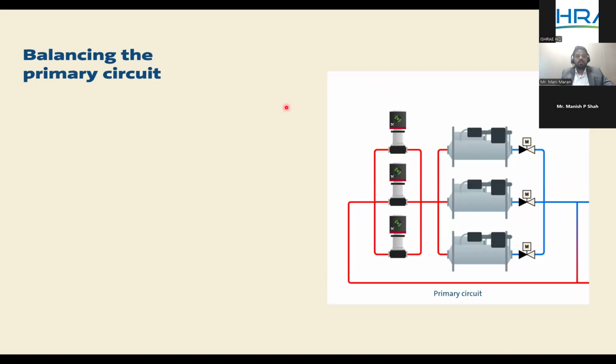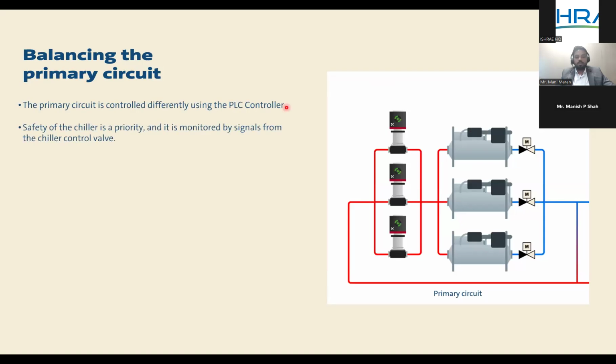So moving back to the primary control, the primary side is controlled by a logic. It can be through a PLC, it can be through a BMS, or it can be through a CPM. So similar to a variable primary system, the chiller minimum flow is critical here. We do the same as we do in a conventional system. The minimum flow of the chiller will be maintained by locking the speed of the pump and by ensuring that minimum flow is always fed into the chiller.